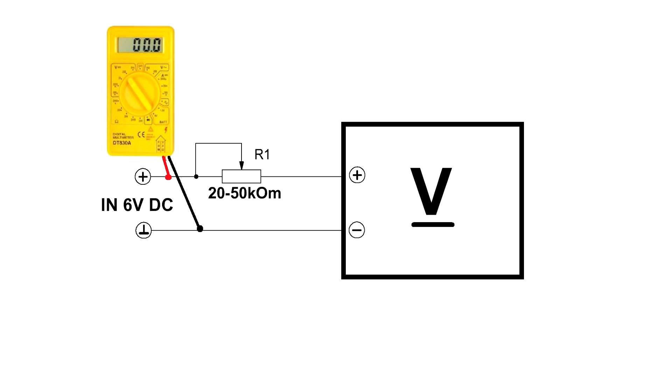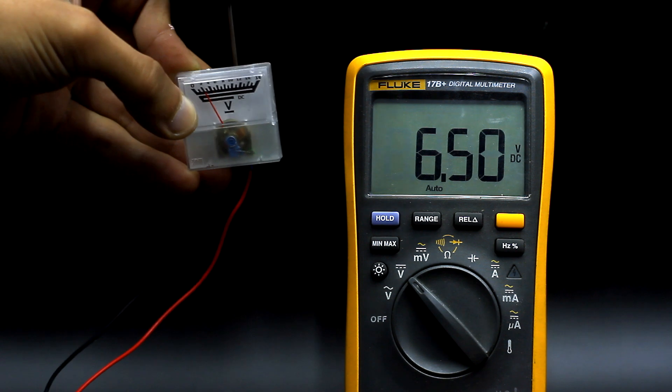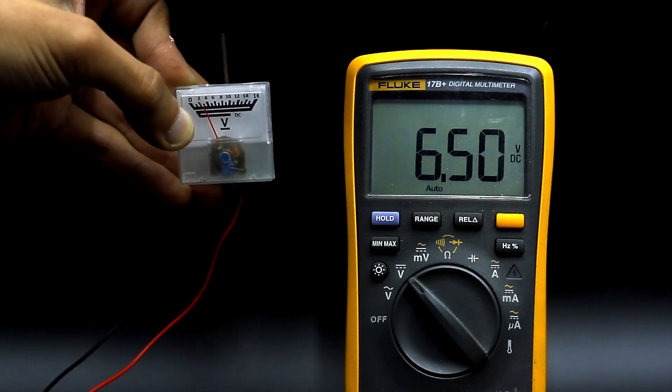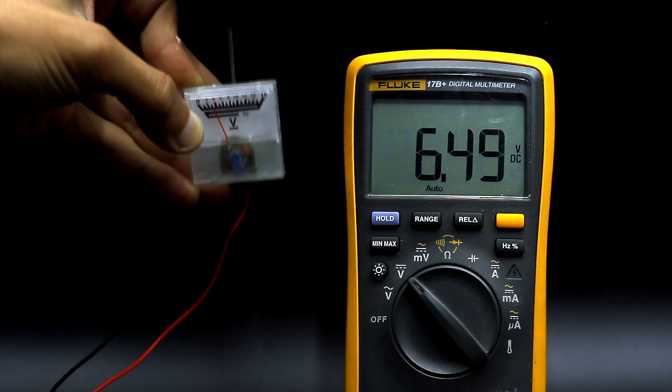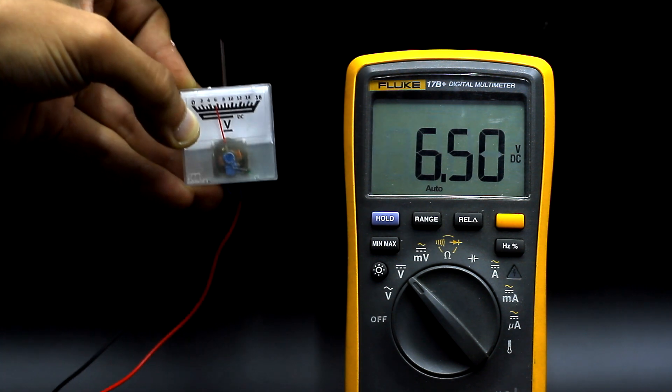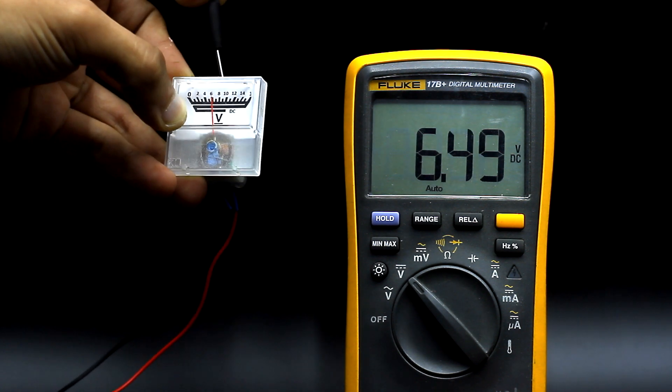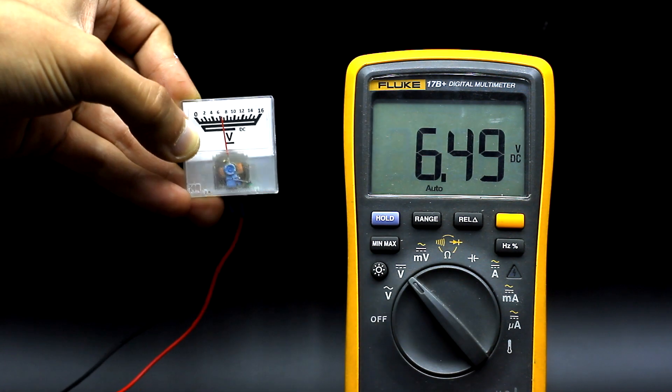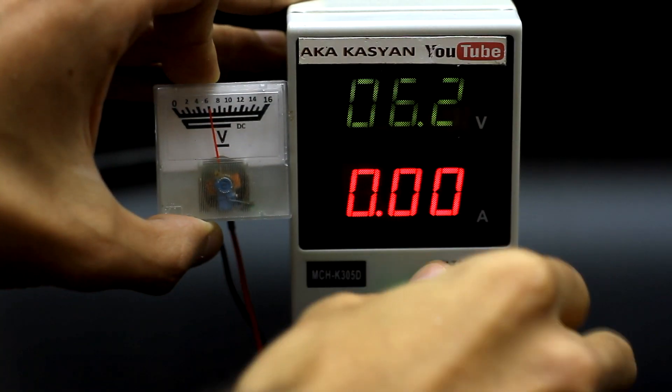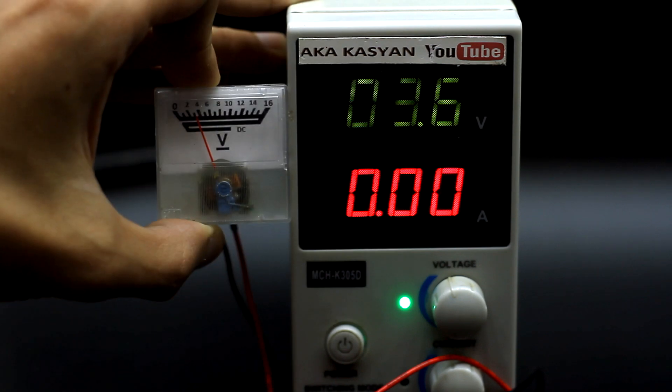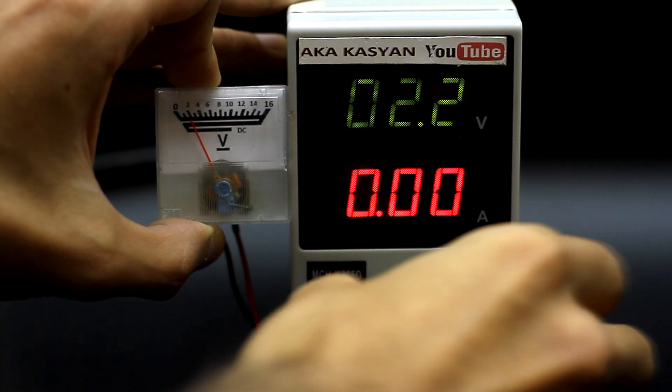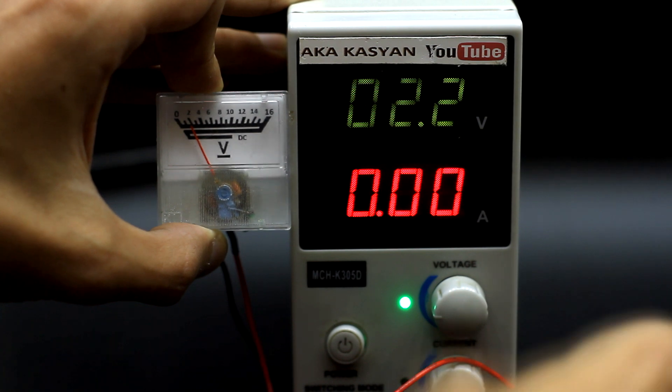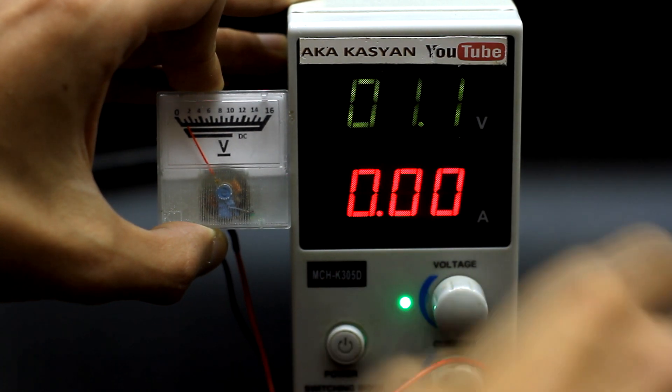In parallel to it, we connect the multimeter. We will have it as a standard to compare. We apply voltage to the input and slowly rotate the trimmer until the arrow shows the voltage that we see on the multimeter. That is, it's enough to calibrate the head at one specific point and due to the linear scale, our meter will also adequately show other voltage values.